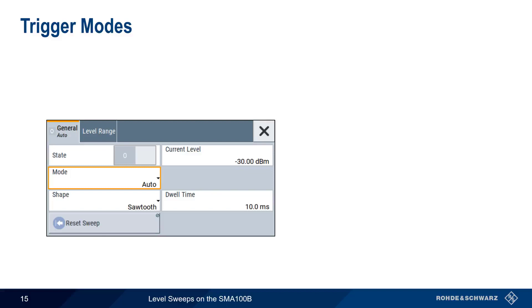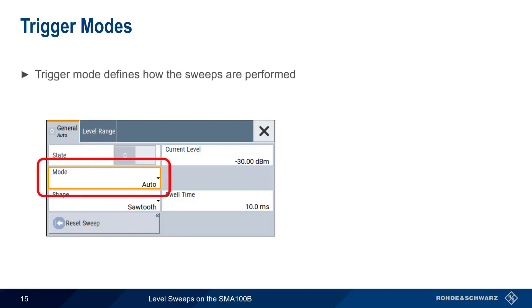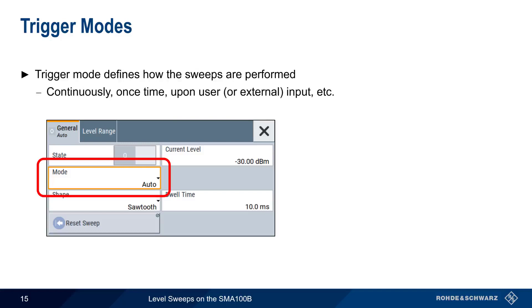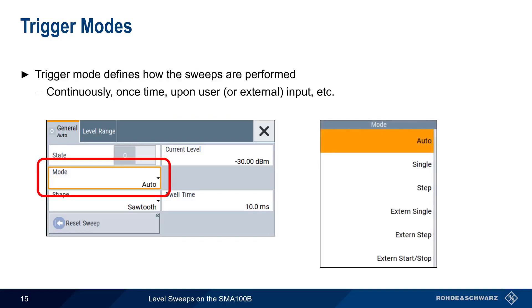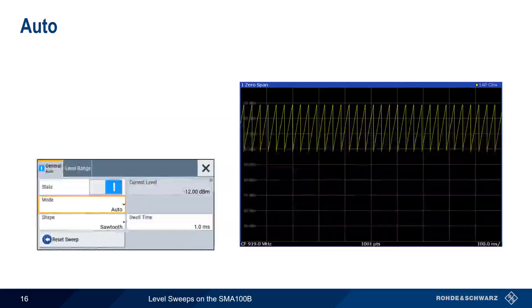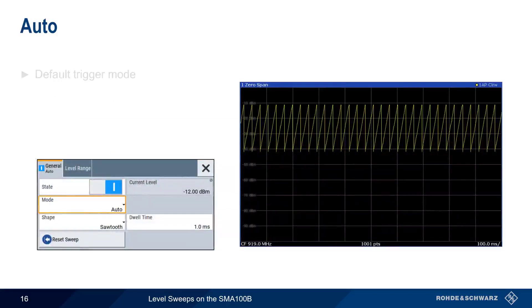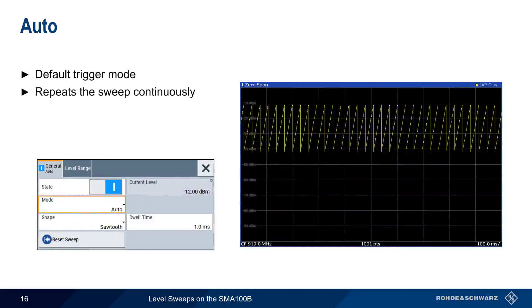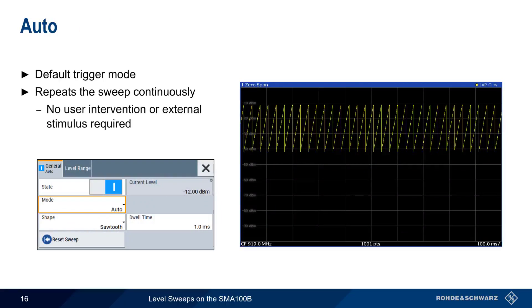The other important configuration parameter for level sweeps is Trigger Mode. Trigger Mode defines how the sweeps are performed, that is, if they are repeated, run only once, run upon user or external input, etc. There are numerous trigger modes on the SMA100B, so let's take a moment to go over each of them. Auto is the default trigger mode and causes the sweep to repeat continuously. No user intervention or external stimulus is required.